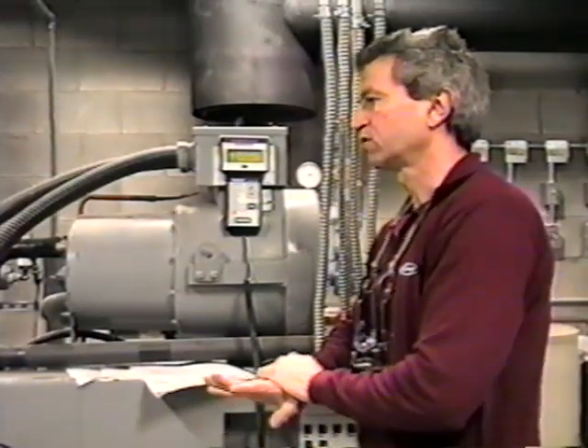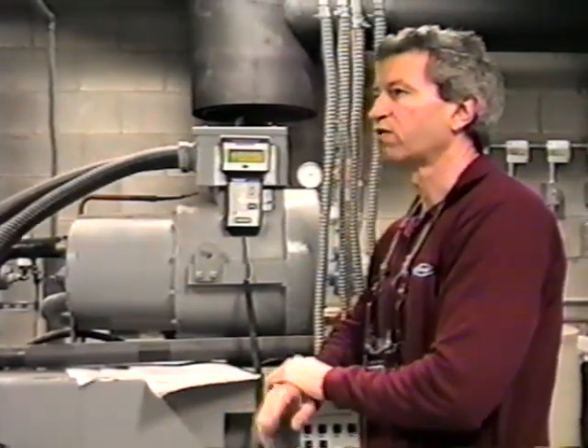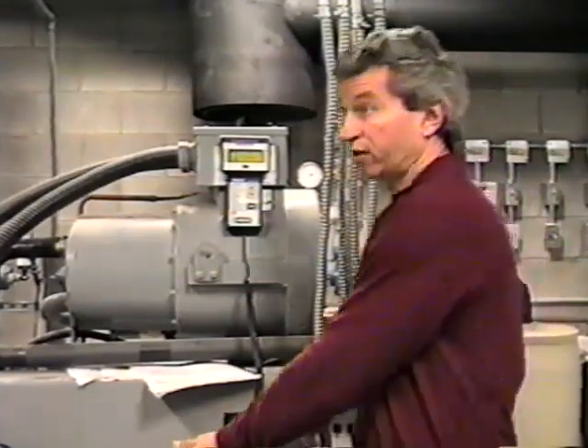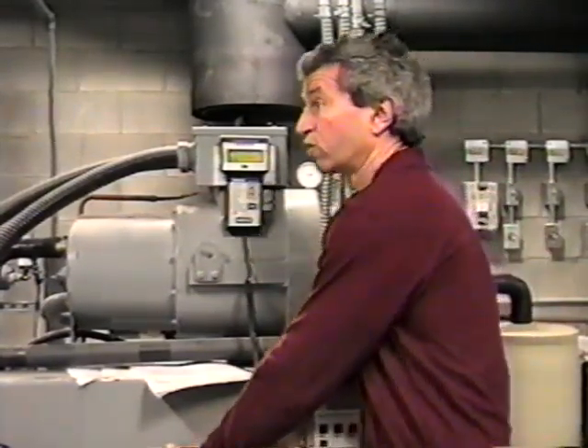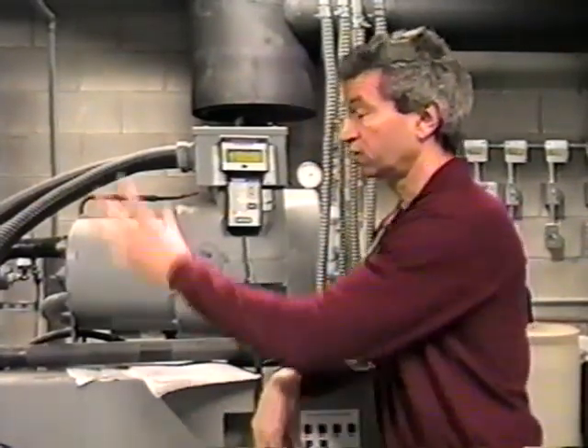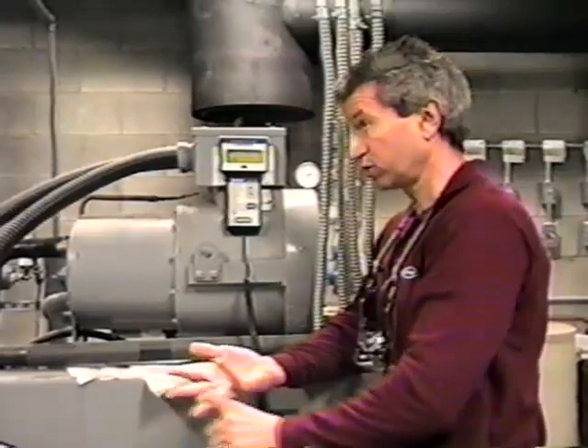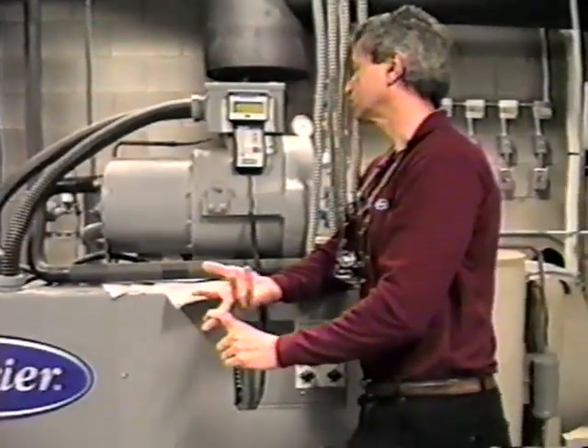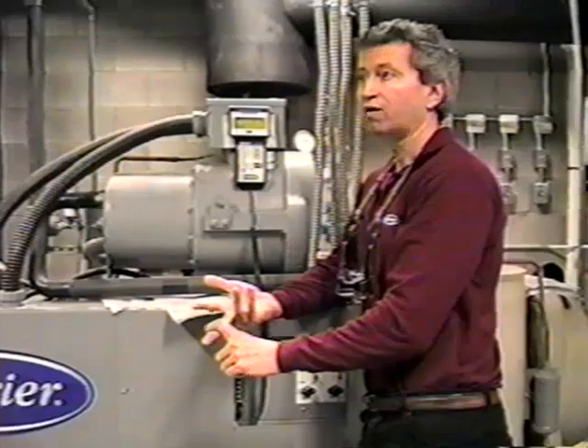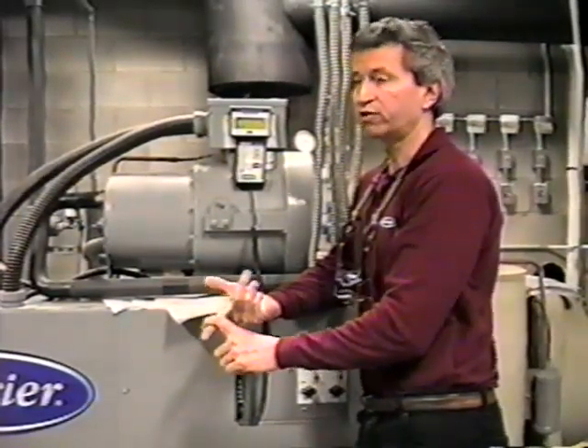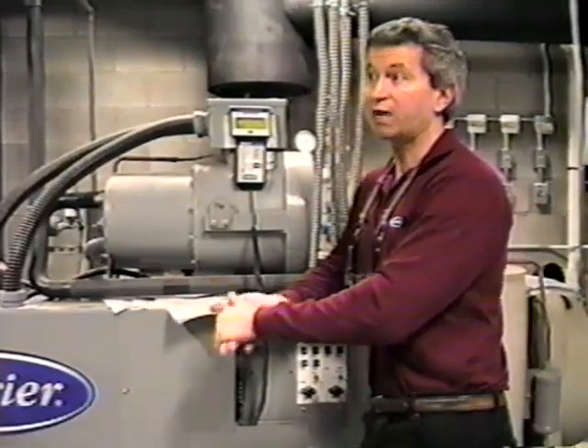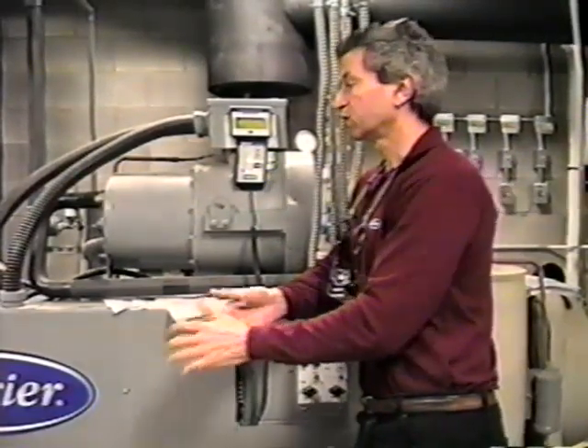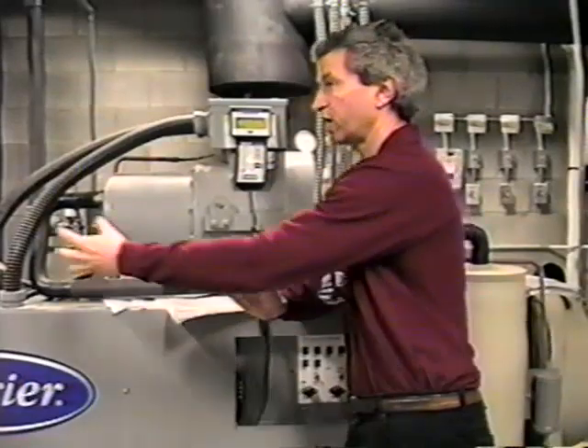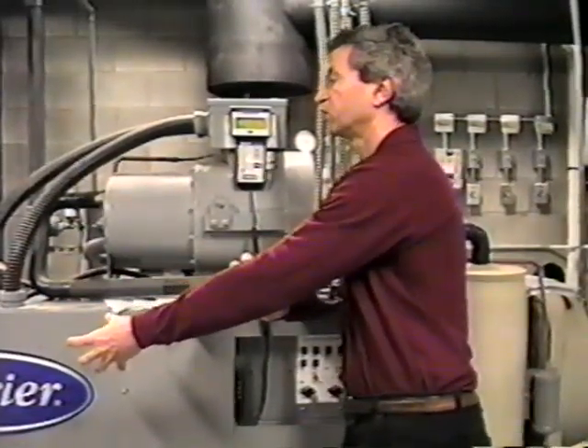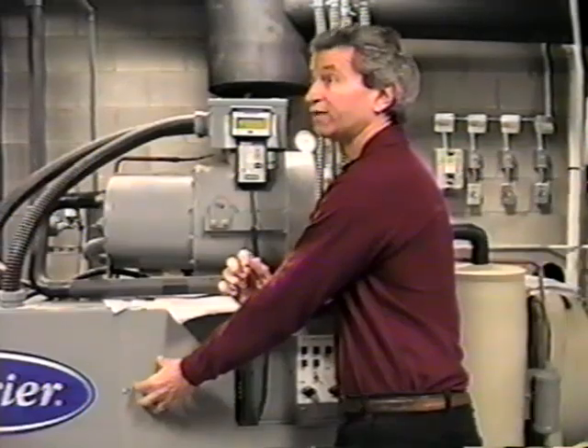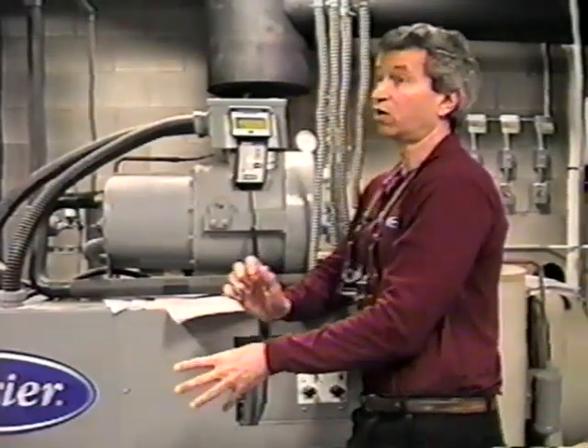There are some alarms, let me pre-qualify that, that are related to the compressor protection module, one of the boards that controls the outputs to the compressors, such as start, stop, or pulling the contactors in. It monitors amperage. It monitors phase imbalance and things of that nature, all the electrical characteristics of an operating compressor. If that particular board senses an alarm, because that information is put directly into the brains of that board, that board can go into an alarm.